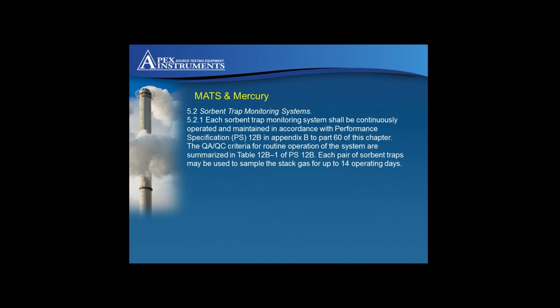PS12B specifically states each sorbent trap monitoring system shall be continuously operated and maintained in accordance with the performance specification PS12B. The QA/QC criteria for routine operation of the system are summarised. Each pair of sorbent traps may be used to sample the gas for up to 14 operating days. However, in our experience, it is more common that we see sample runs of 7 days, as particulate matter build-up and other factors prohibit most sources from running for 14 days.